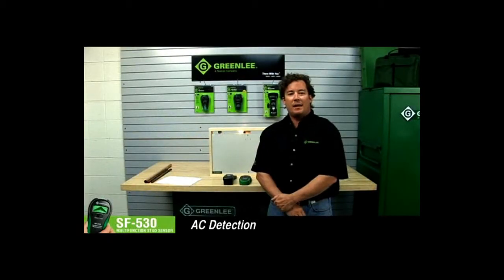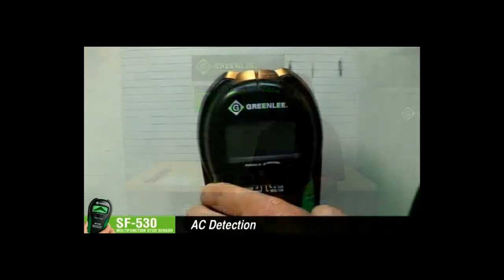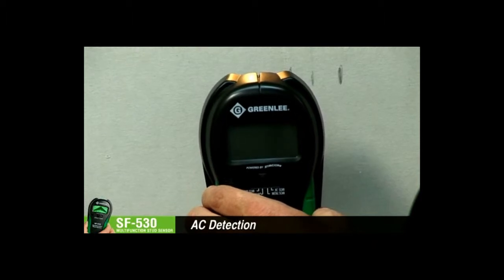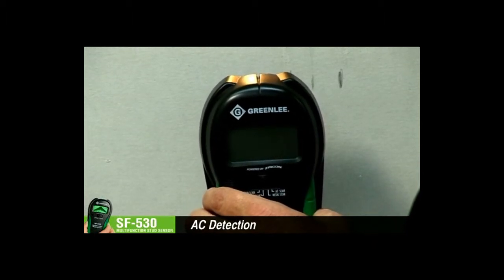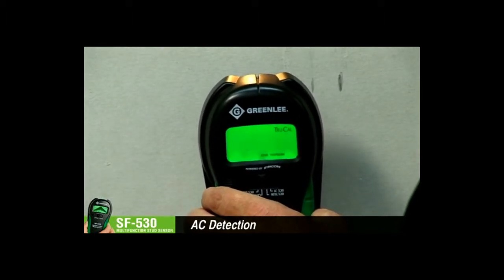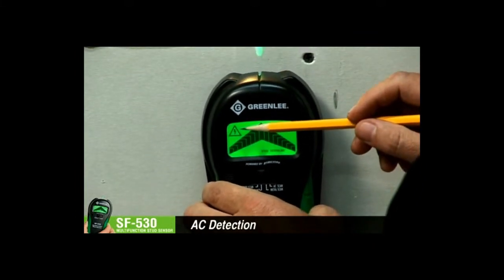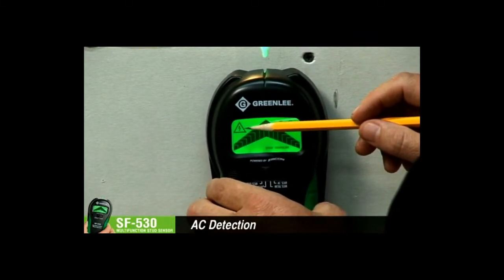AC detection can detect hot AC current behind a wall or floor before you screw or saw into it, which is much safer. AC detection will not find hot AC current inside metal conduit. AC detection is always on for safety. On the SF530, the lightning bolt in the triangle comes on when you get near hot AC current.